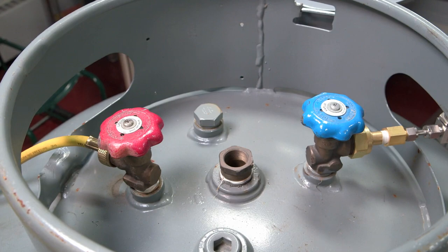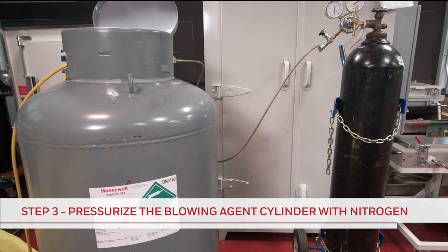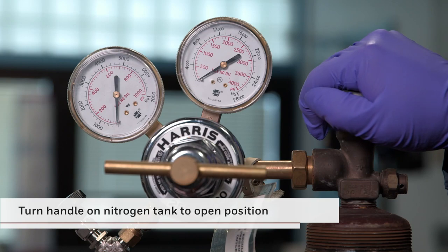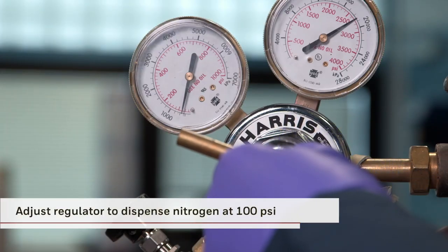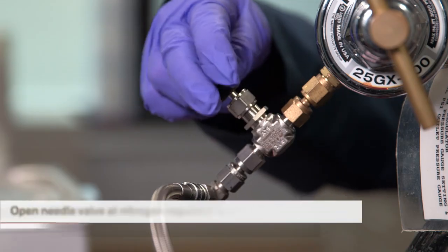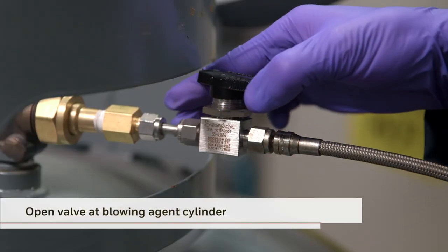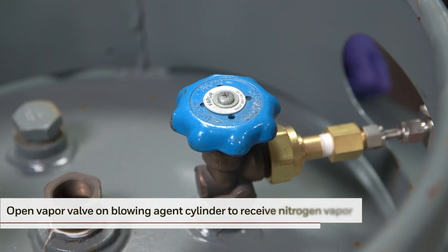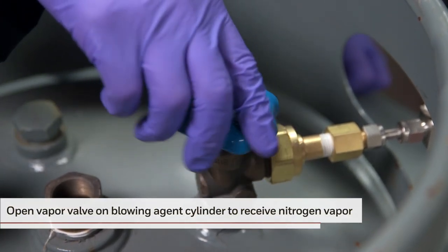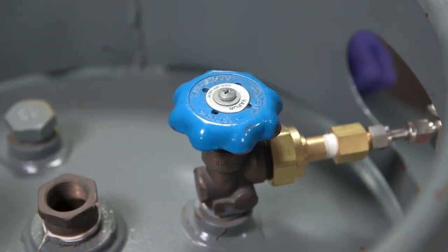You're now ready to begin the pressurization process. Now that the lines are connected, the process of pressurizing the blowing agent cylinder can begin. First, turn the handle on the top of the nitrogen tank to the open position. Adjust the regulator to dispense the nitrogen vapor at 100 PSI pressure. Now, open the needle valve at the nitrogen regulator. Next, open the valve on the nitrogen line near the blowing agent cylinder. Then open the vapor valve on the blowing agent cylinder to allow the nitrogen vapor to flow into the cylinder and pressurize it. This completes this stage of the pressurization process.